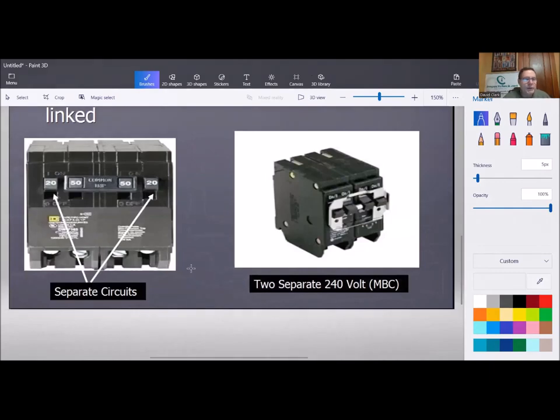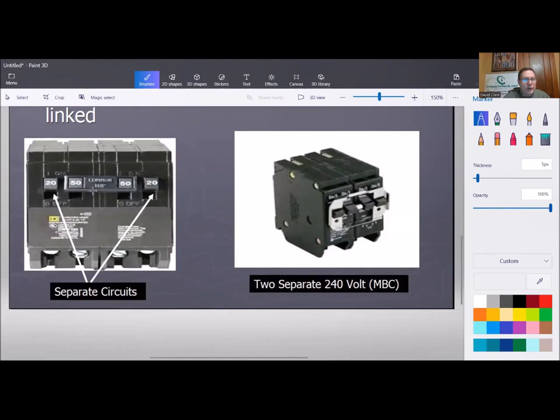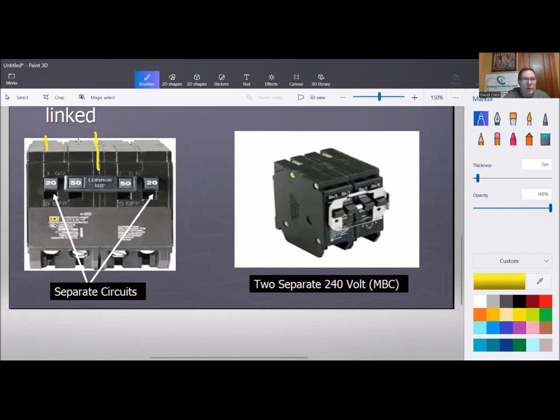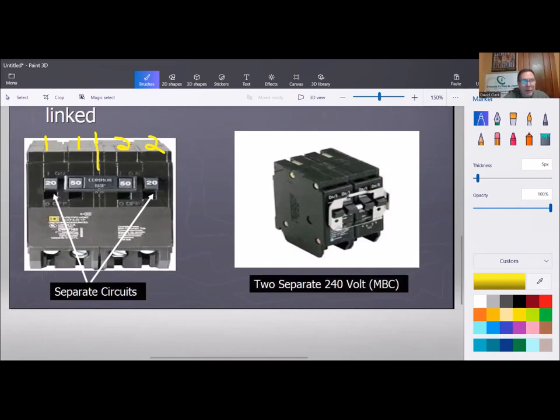So there's two different scenarios and this works great. So if you look here now, we'll see the centers are connected. Again, same situation. I'm going to go back to the yellow. And so here are our two legs. We've got leg one here, leg one here, leg two, leg two. So no problem connecting those two together. And there they are. They are a common trip. And it's written right on there. You can see it's a little bit blurry, but trust me, it says common trip, which means that they're externally and internally tripped.